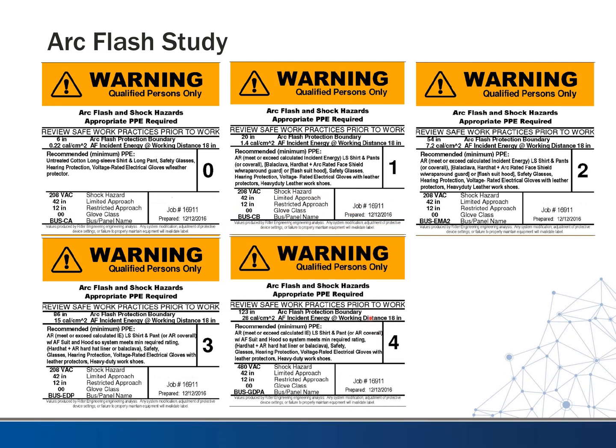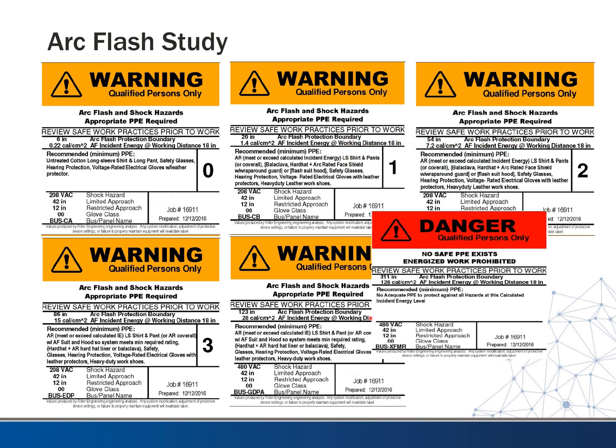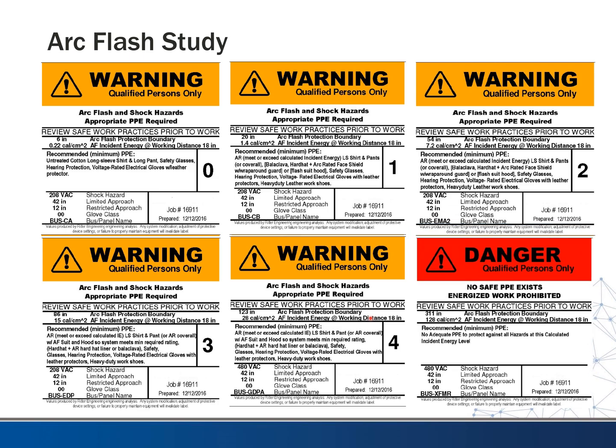Category four is the highest category where you can still find PPE to make it safe enough to work. And finally, if you come across one where there is no safe PPE — which is usually over about 40 calories per centimeter squared — we just say 'dangerous,' there's no safe PPE that exists and energized work is prohibited. You're likely to see these arc flash labels on panels — they're required to give information to keep technicians safe as they work on different pieces of equipment.